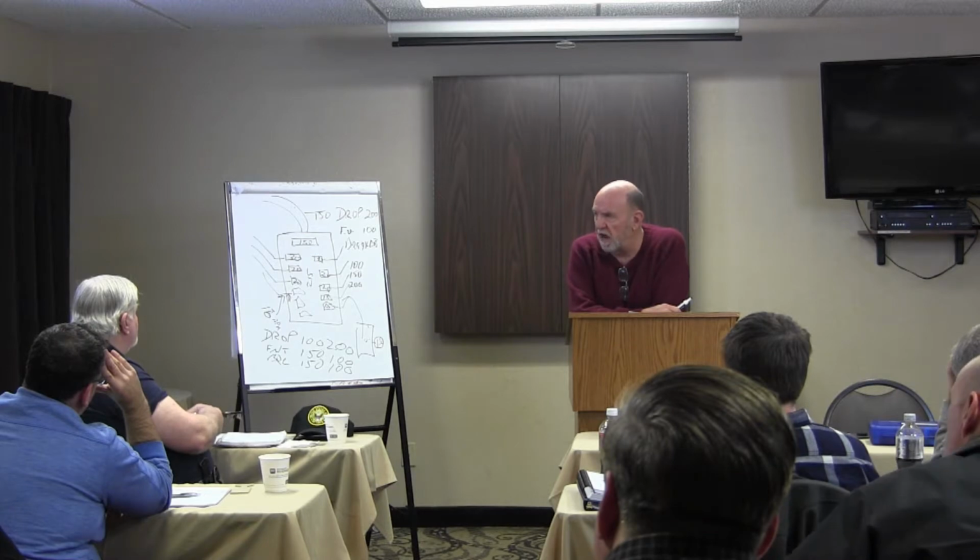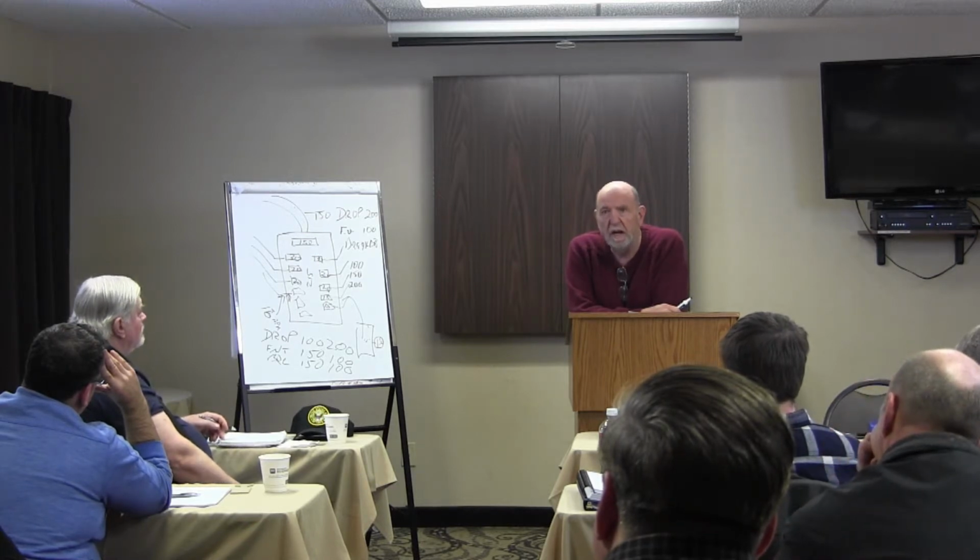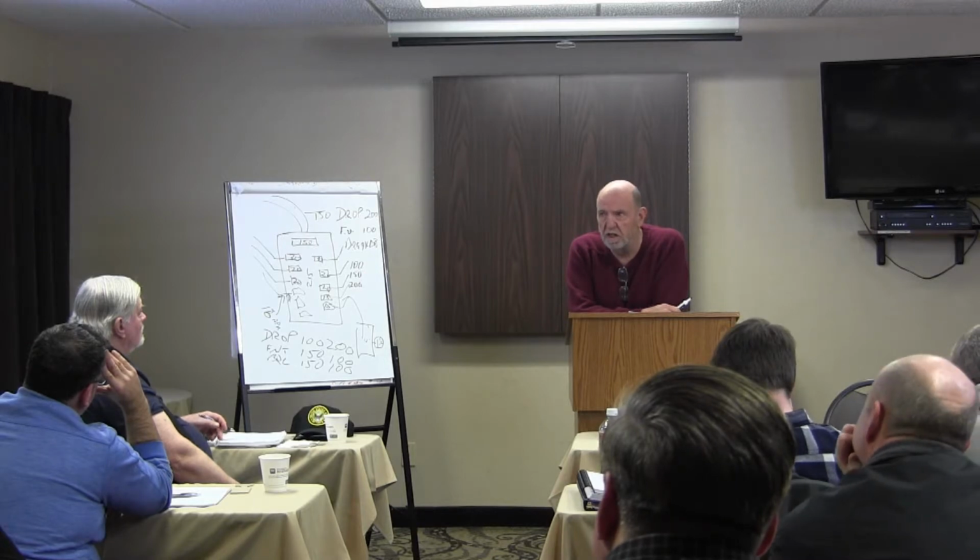If you have a 200 amp breaker and anything lower in the system, that's a problem. The lowest thing determines what size the breaker is. So write your defects up in that manner. Don't say that the lowest thing needs to be changed to higher. Say that the higher breaker needs to be matched to the lowest wire in the system.